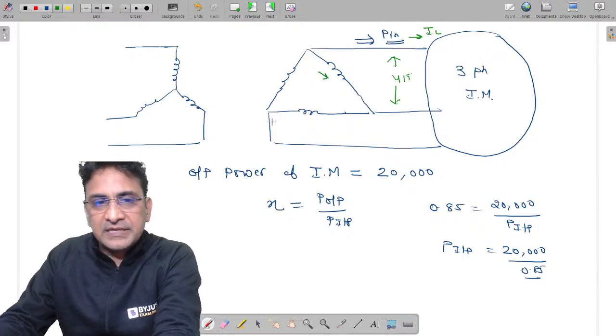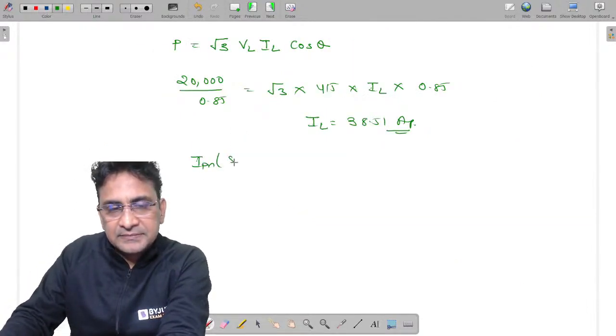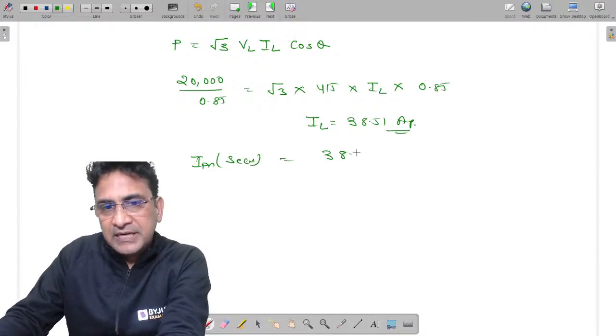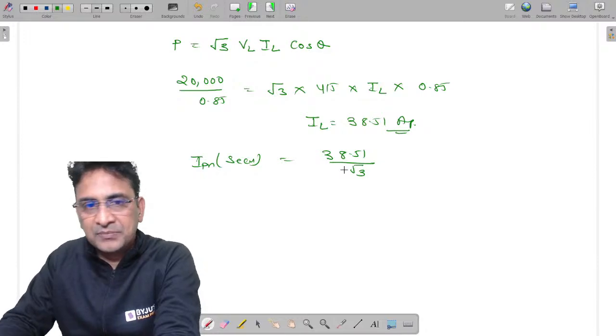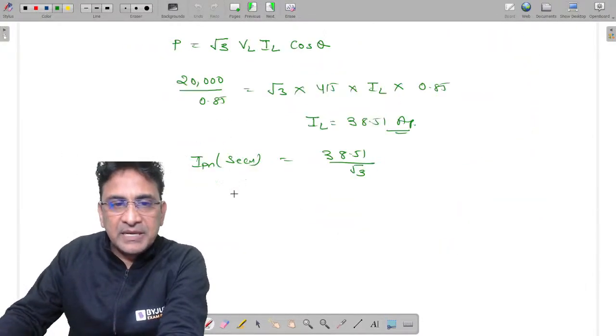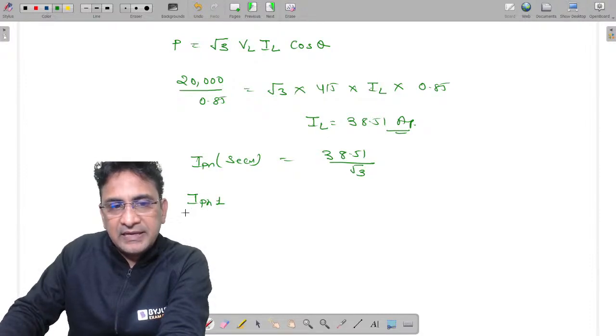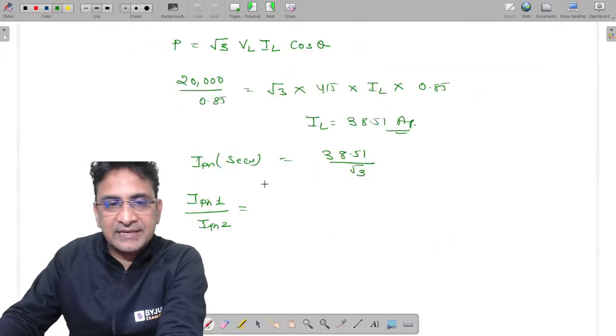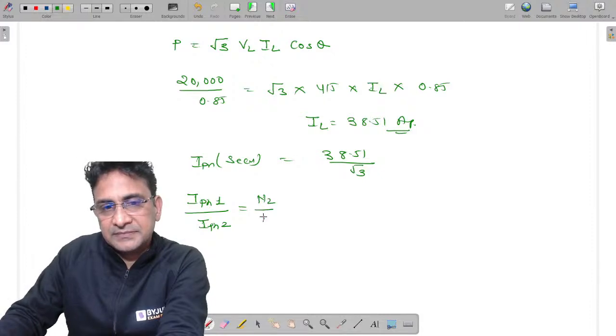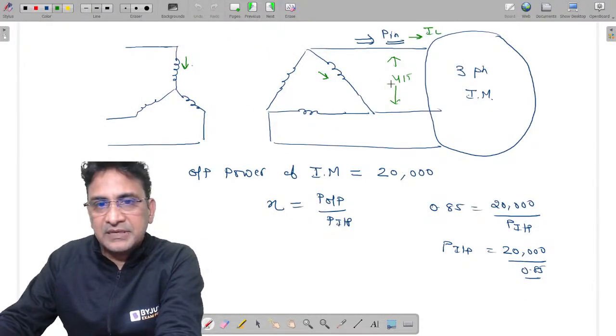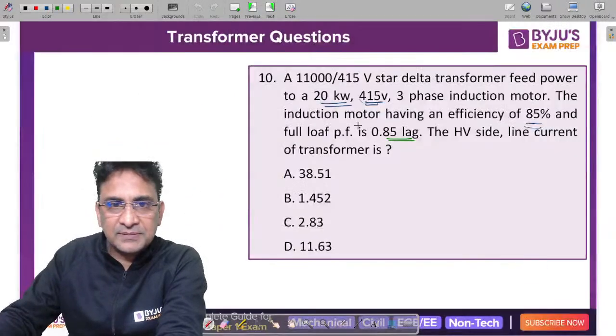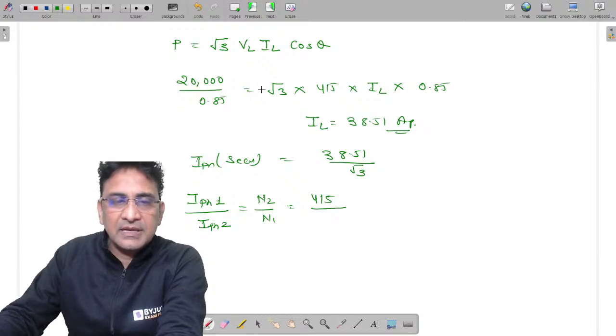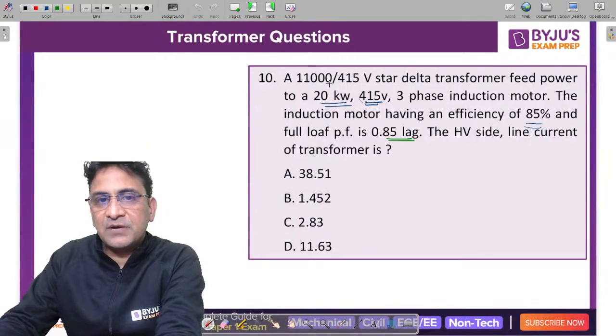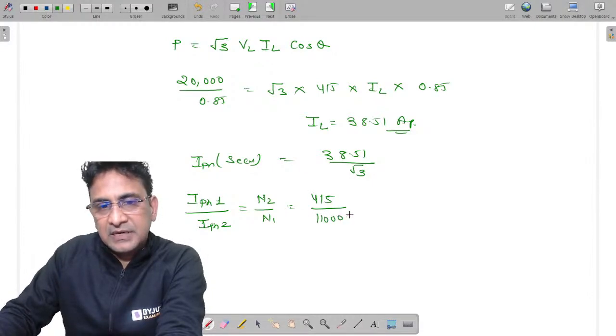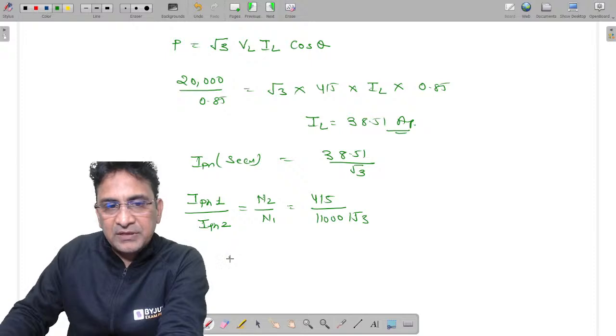So what is the value of phase current? The phase current on the secondary side will be 38.51 divided by √3. Okay. Now what will be the phase current on the primary side? The primary side phase current and the secondary side phase current are inversely proportional to the turn ratio. Secondary side turn ratio will be as per the voltage 415, and for the primary side, 11,000 volt is the line voltage, so it becomes 11,000 divided by √3. So find out the value of IPH1.